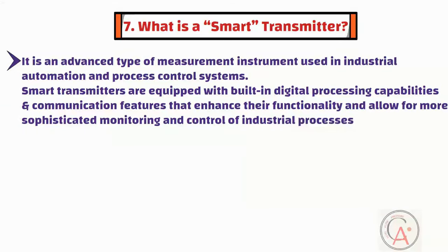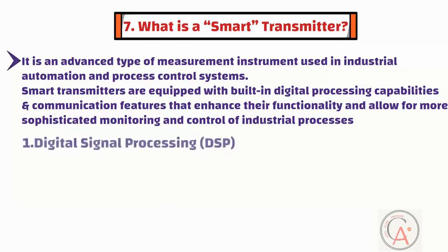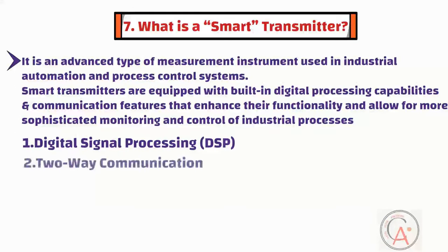Here are the key characteristics and features of smart transmitters. The first characteristic is digital signal processing. Smart transmitters incorporate digital signal processing capabilities, allowing them to perform complex calculations and signal conditioning tasks internally, which helps improve measurement accuracy and reliability. The second characteristic is two-way communication. Smart transmitters are capable of two-way communication with control systems and other devices. They can transmit measurement data to a central control room and receive commands or configuration updates remotely.